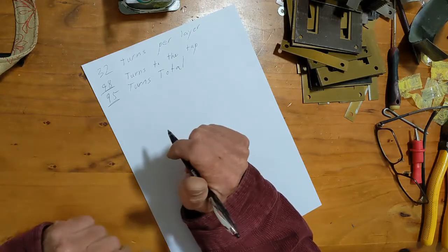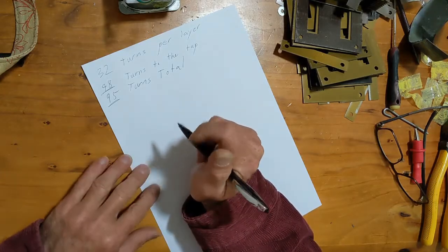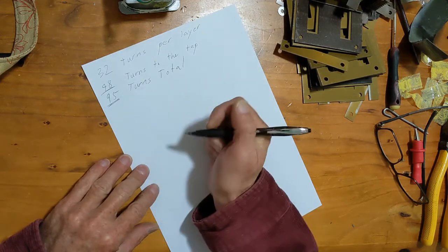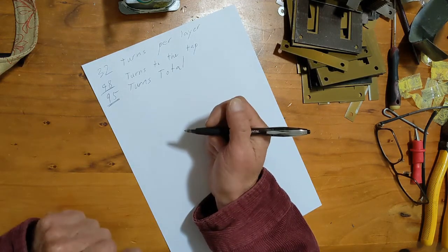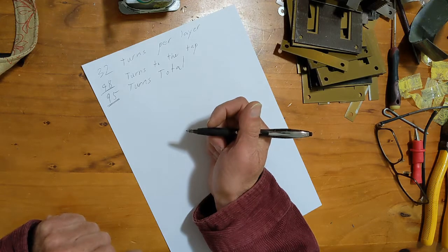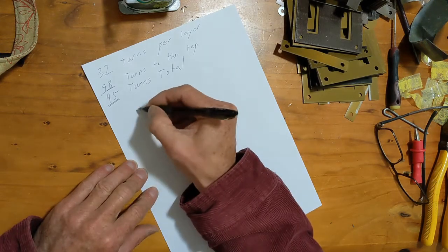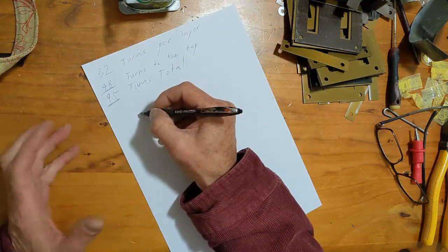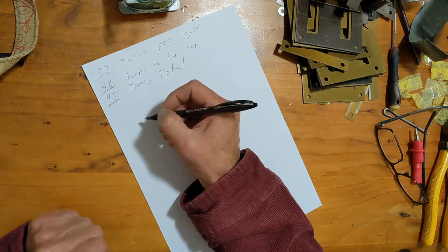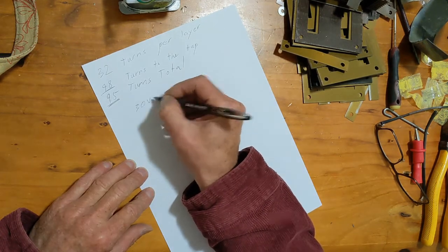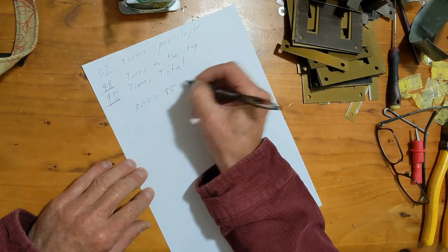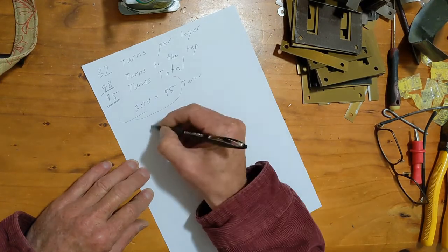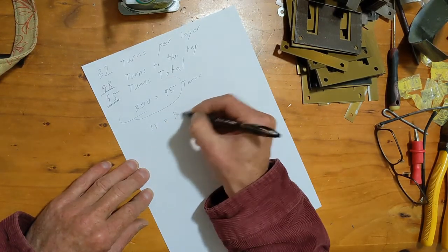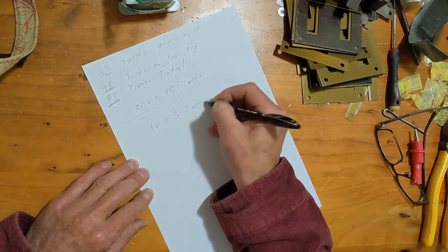We know that this was a 30 volt transformer. We know that we had 95 turns on the low voltage side of the transformer. So from there, because we know that the turns ratio and the voltage ratio are the same, we had 30 volts equals 95 turns, so 1 volt equals 3 turns.